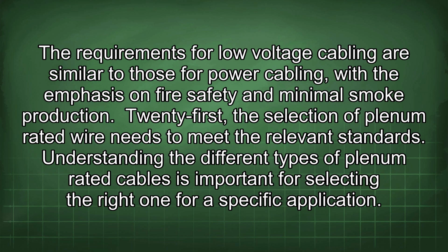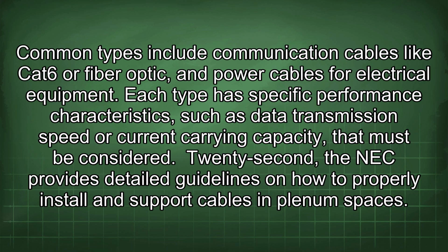21st, the selection of Plenum-rated wire needs to meet the relevant standards. Understanding the different types of Plenum-rated cables is important for selecting the right one for a specific application. Common types include communication cables like Cat6 or fiber optic, and power cables for electrical equipment. Each type has specific performance characteristics such as data transmission speed or current carrying capacity that must be considered.